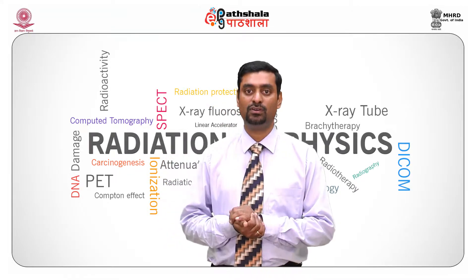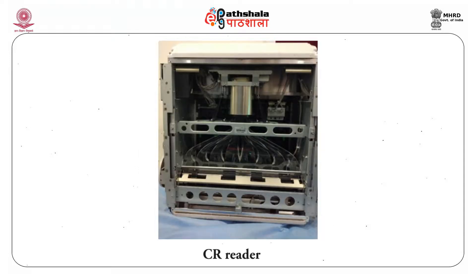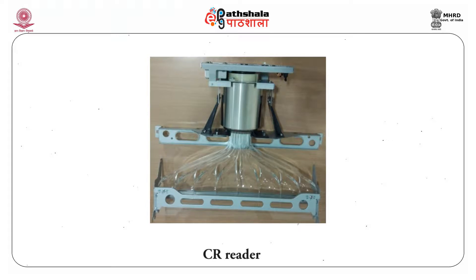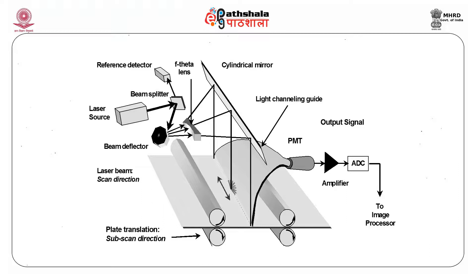The IP plate containing the latent image is fed into a CR reader. Inside the CR reader is a helium-neon laser which gives red light. This photograph shows the internal components of a CR reader including a laser assembly and optic coupling. The CR reader has a laser source and a beam splitter — one part of the beam goes to a reference detector and the other to a beam deflector. From the beam deflector, the beam is deflected to an f-theta lens, then to a cylindrical mirror, channeled through a light guide, and absorbed by a photomultiplier tube. From the photomultiplier tube it goes to the amplifier and then to an analog-to-digital converter for processing.